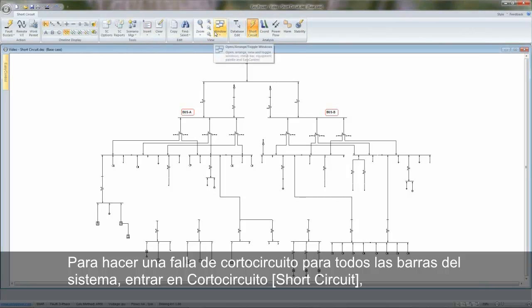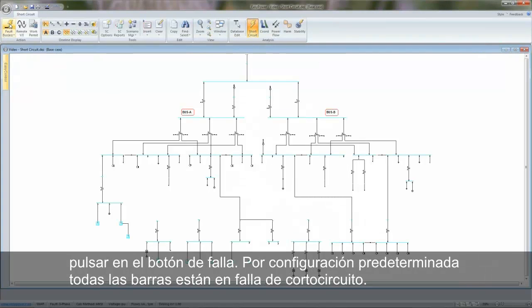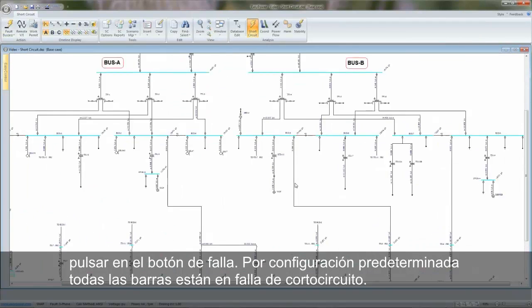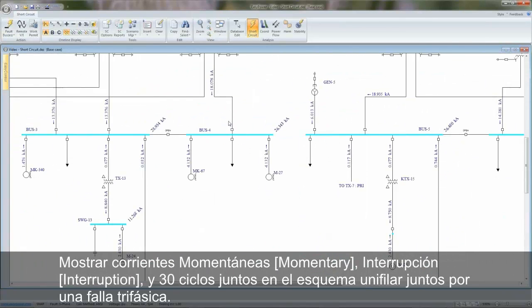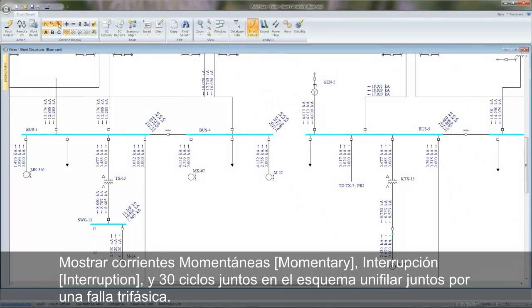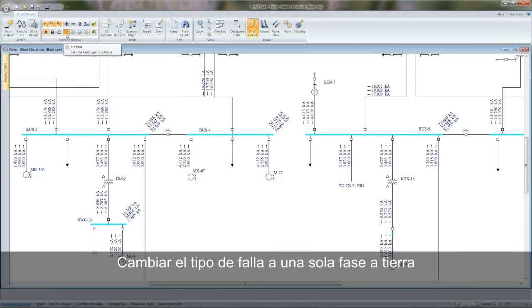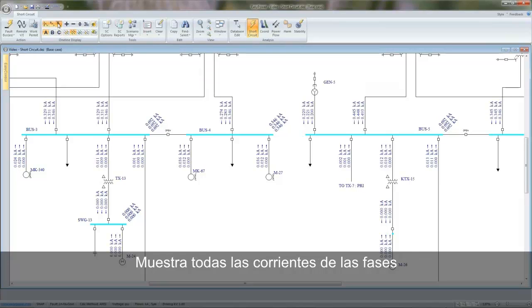enter Short Circuit and click on the Fault button. By default, all buses are faulted. Show momentary, interrupting, and 30-cycle currents together on the one line for a three-phase fault. Change the fault type to single line to ground. Show all phase currents.